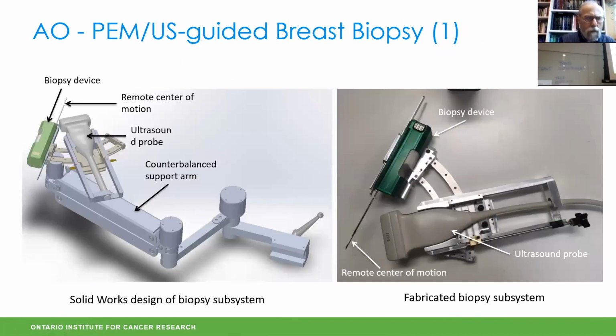So the end effector is the ultrasound transducer, ultrasound probe, and the biopsy device. So this is a unique design. It has a remote center motion, which means that the center line of the ultrasound transducer and the needle, the biopsy, the center of the core coincide, which means if we place the mechanism such that the remote center motion is centered on the lesion, then we can guide a needle to a target.